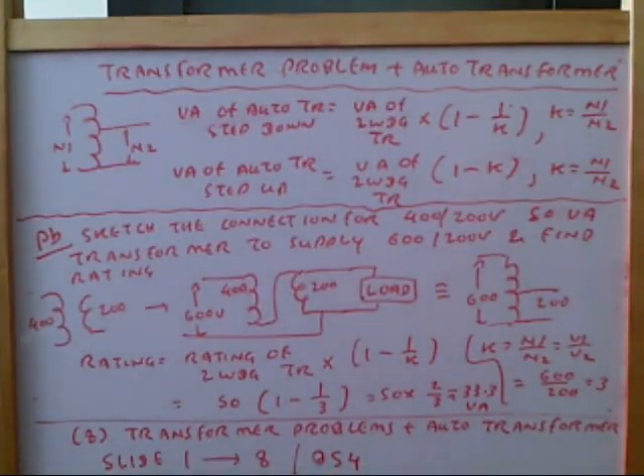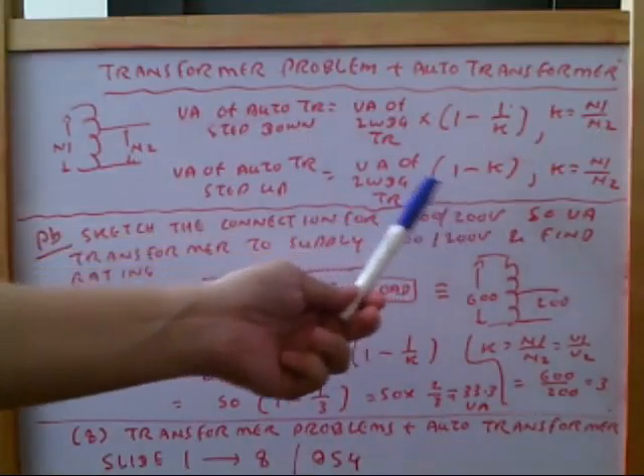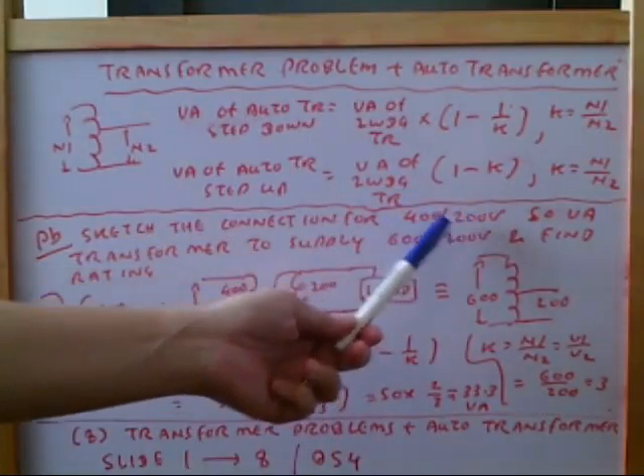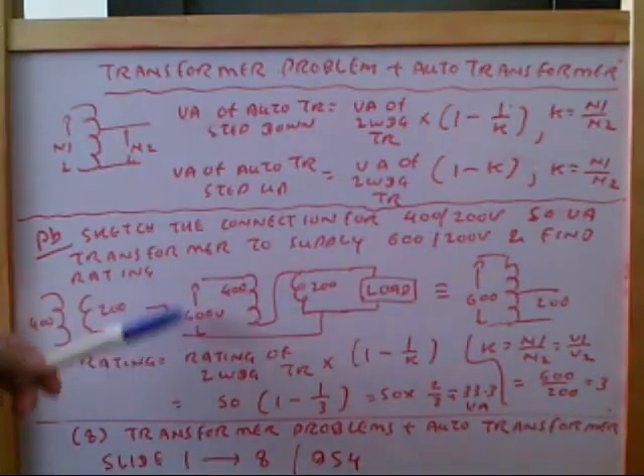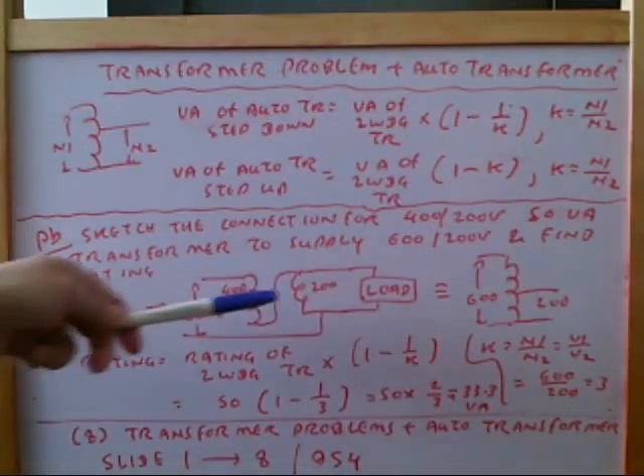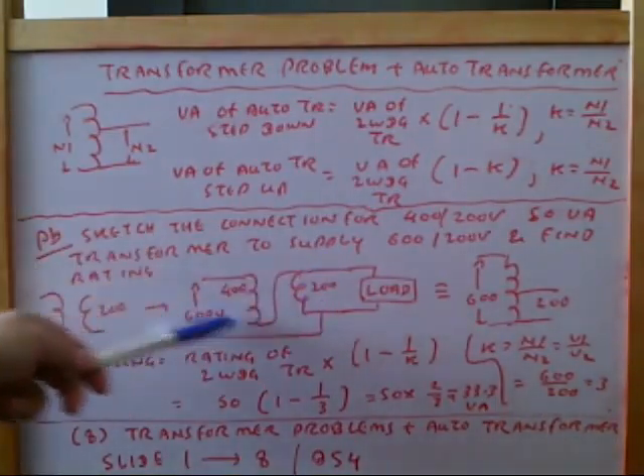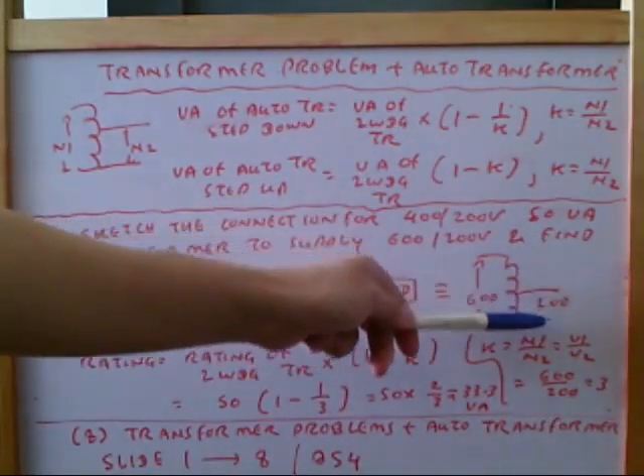So to withstand the 600, you have to connect the 400 and 200 in series for the primary. So this is 400 and 200 in series for the primary VA. So the voltage for them will be 600 volt. But secondary, 200 volt is applied. So the circuit is redrawn as primary is 600 and secondary 200.